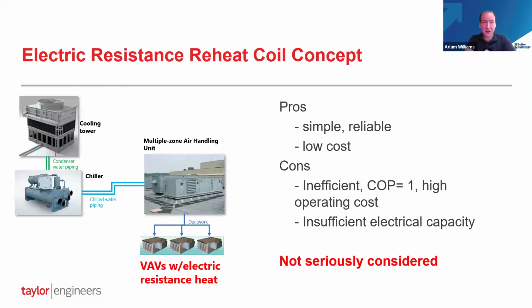Next slide. So we started looking at some concepts. I'm going to go over this. Initially, we looked at electric resistance heat very quickly, because the idea is, well, if we're going to replace out the terminal units, we could just put in electric resistance heating coils. And it's simple, fairly low cost, but it's not very efficient. For every unit of electric power you put into those, you get 1 unit of heat out, which isn't very efficient. And the existing electrical capacity at this building could not provide full electric resistance heat for the whole building. So it wasn't going to work electrically, and it's not really allowed in the Title 24 California Energy Codes for this approach. So we didn't seriously consider this, but I'm pulling it up because that would be the challenge with electric resistance heat: electrical capacity and efficiency concerns.